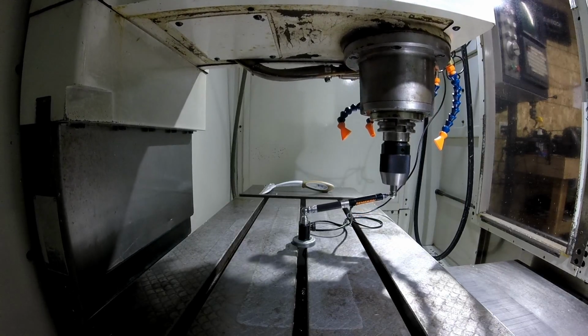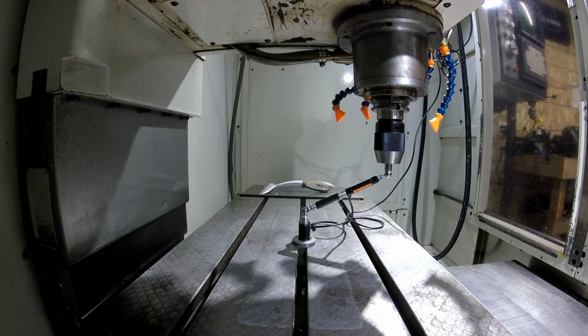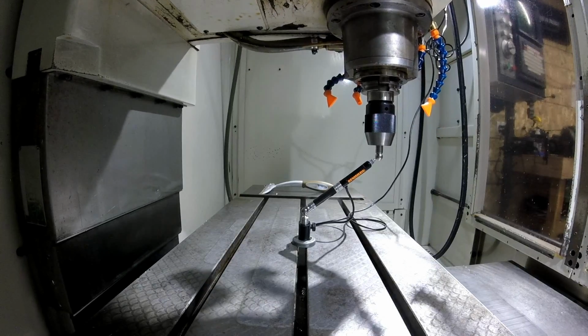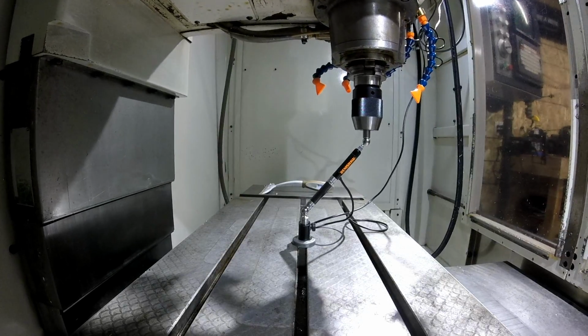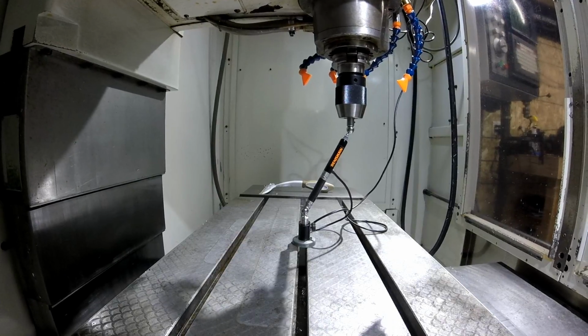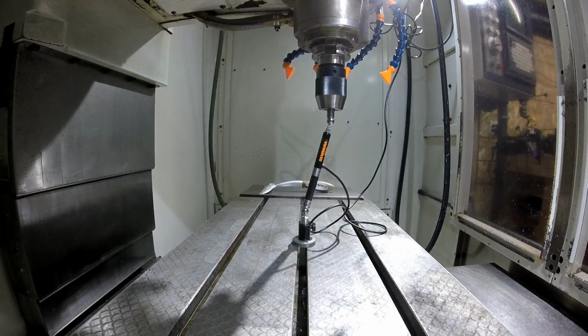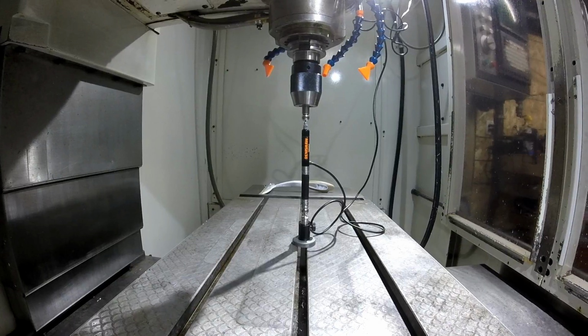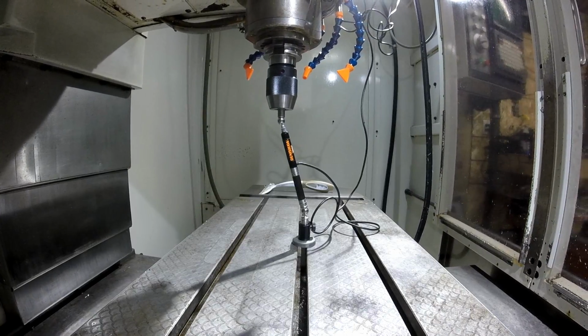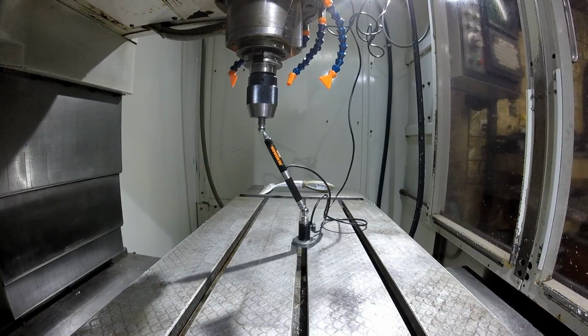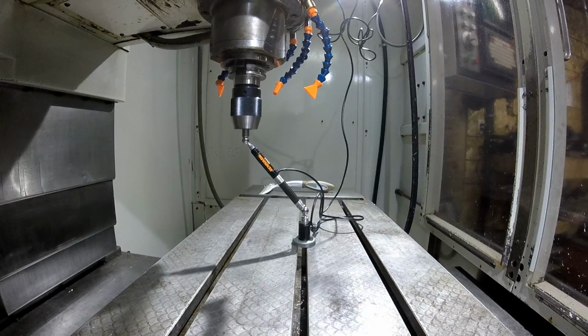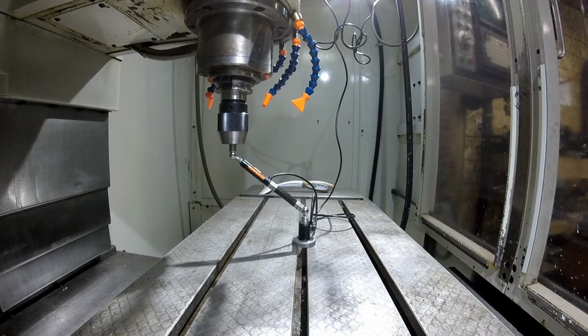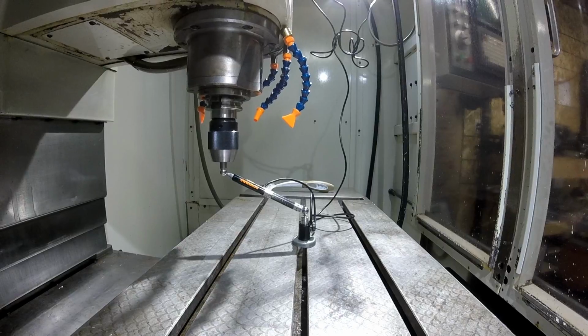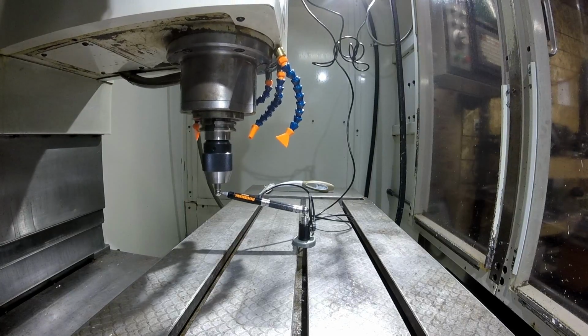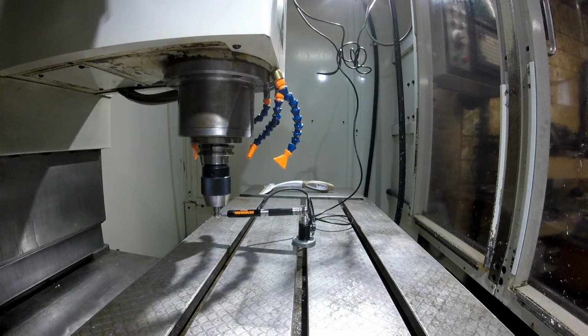If it's bad, what Brian will do is he'll redo the setup so that the magnetic base that's on the table, now facing up, will face sideways, and then there's a different attachment for the spindle so that he can do a full 360-degree sweep in the YZ or XZ planes. And then by doing a full 360-degree sweep, that's how you can get the full detailed information that we saw in the XY sweeps of squareness and all of that.